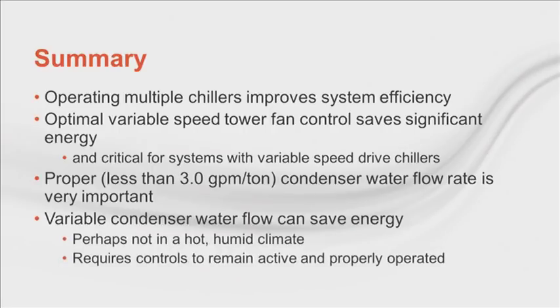After looking at other building types and locations, the conclusions seem to hold true, except variable condenser water flow may not save energy in very hot and humid climates. And we do have some concerns that the controls may be modified or turned off at some point in the life of the plant, so the savings are less certain for variable condenser flow systems than for low flow optimized constant flow condenser water systems.